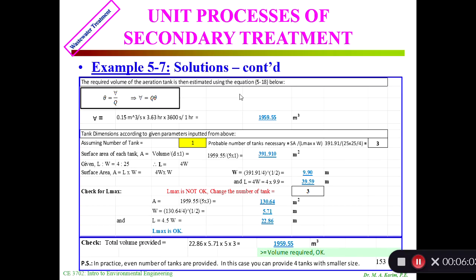From there we'll calculate the volume using equation 5-18: volume equal to Qθ. The volume I got is 1959.55 m³. Now I'm going to do the design. Initially I consider one tank with depth of 5 meters. I calculate the surface area would be equal to volume divided by depth, which equals 391.9 m². Let's consider L to W equal to 4:1, so L = 4W.